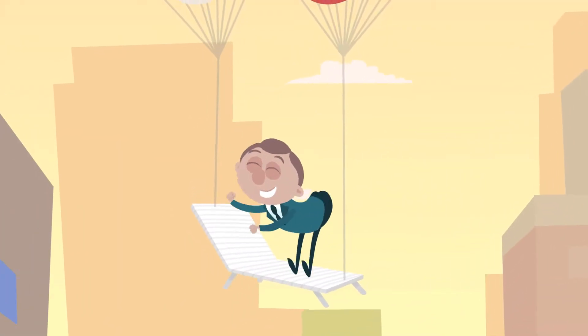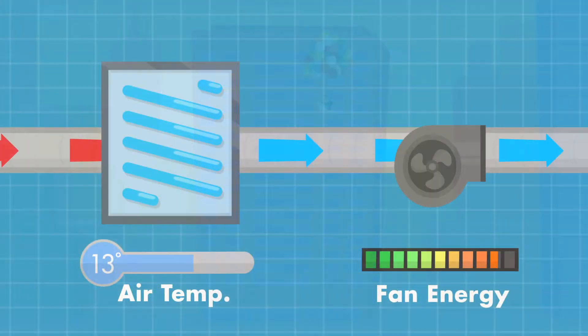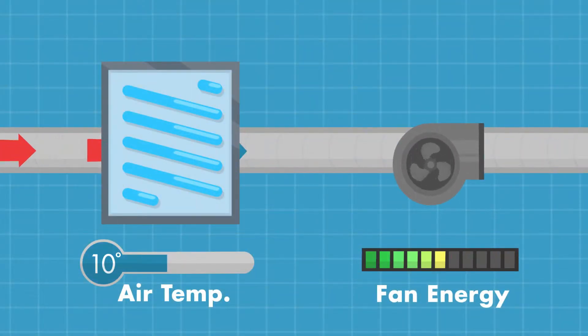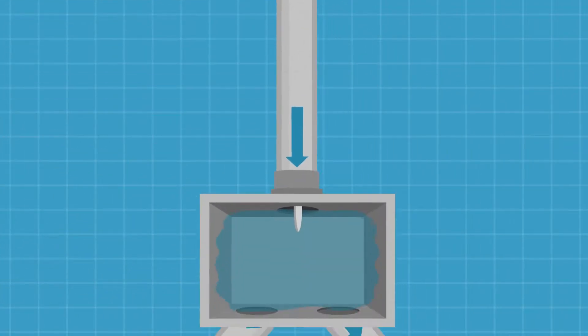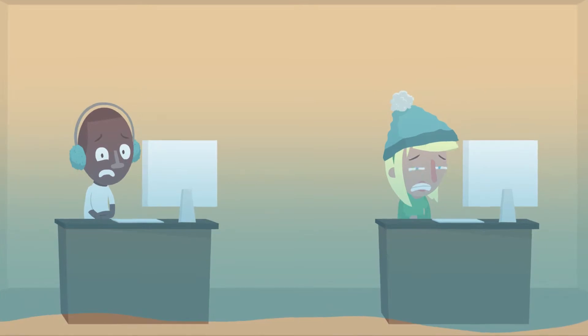You look pretty excited Albert! Here's one of Albert's older properties, cooled by a traditional VAV system that's now using lower temperature primary air to conserve fan energy. But low primary air temperatures on a VAV system tend to cause dumping and poor air circulation and tenants don't like that.